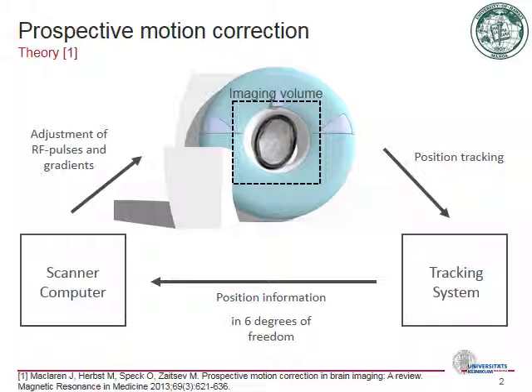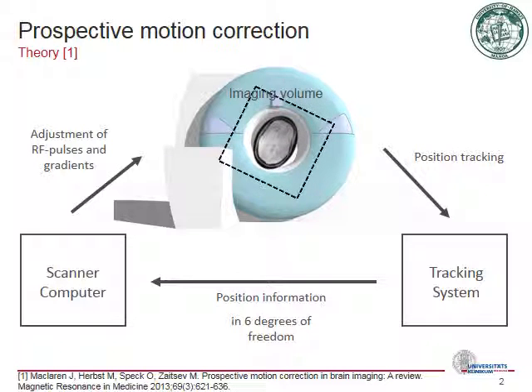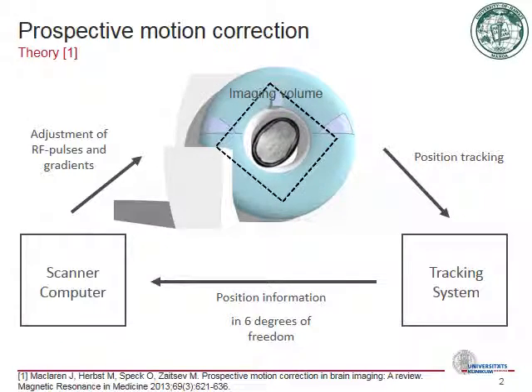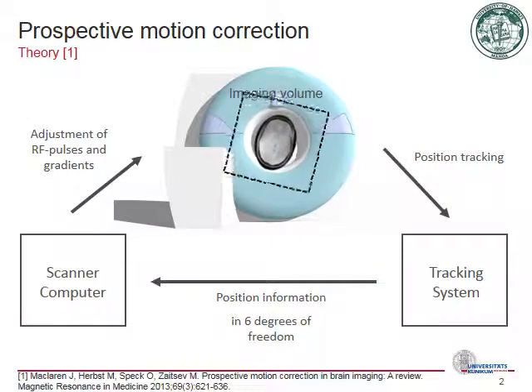where all gradients and RF pulses are adjusted in real time. This is equivalent to moving the imaging volume with the subject so that there is no relative motion between them, and the resulting images show no motion artifacts.